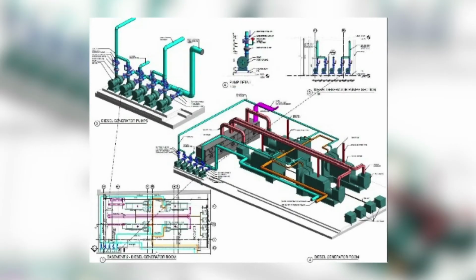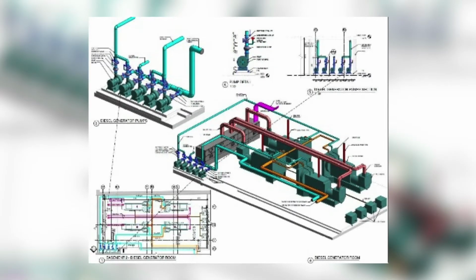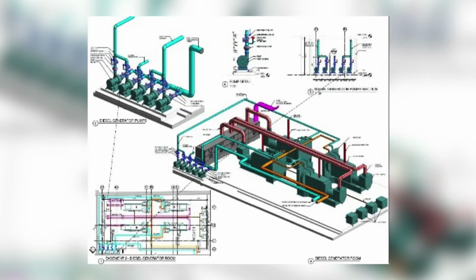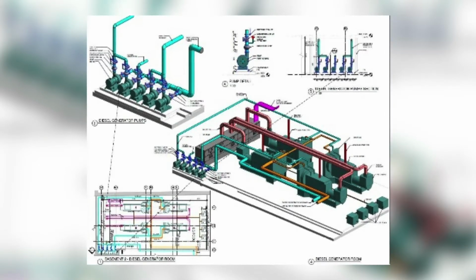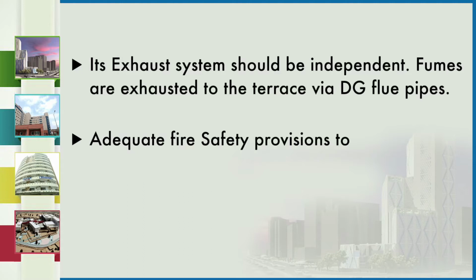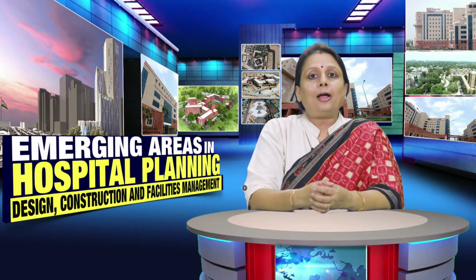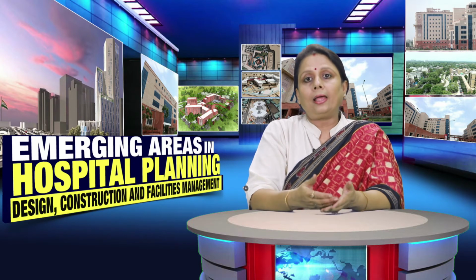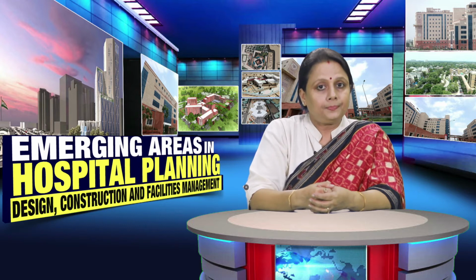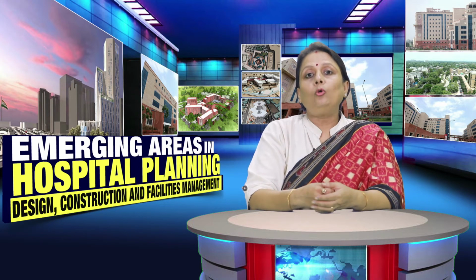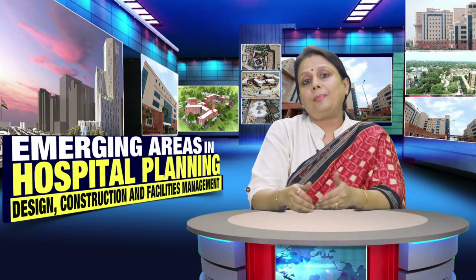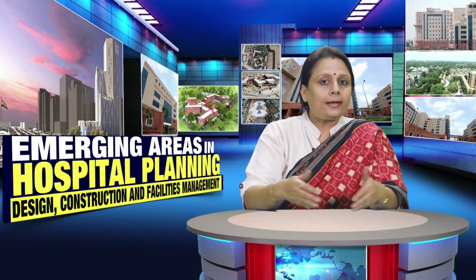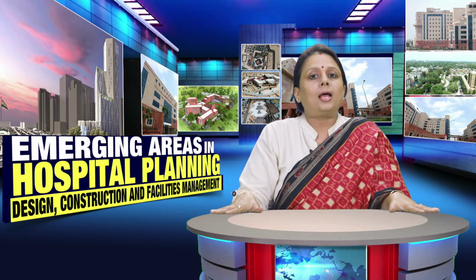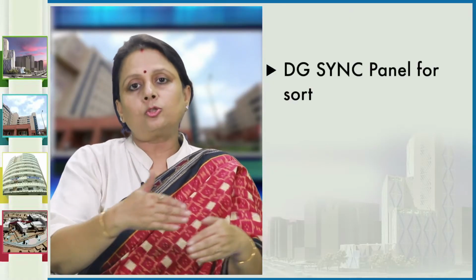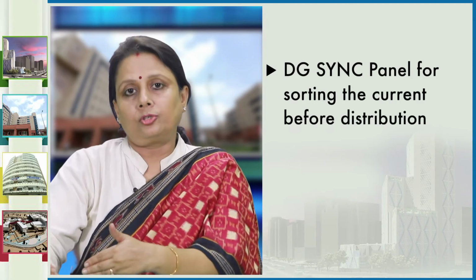In the diagram here, we can see the generator being fed by the diesel pipes, the flue pipes for exhaust and its sync panel. Fire safety provisions for DG rooms are to be made adequately. If people remember the tragic fire of Upahar cinema, which consumed many lives, it is believed to have started with the DG. Now the DG will have its own DG sync panel, meaning DG synchronization panel. The power from DG is collected at this panel and distributed to each area as per requirement. So it is used for sorting the current before distribution.